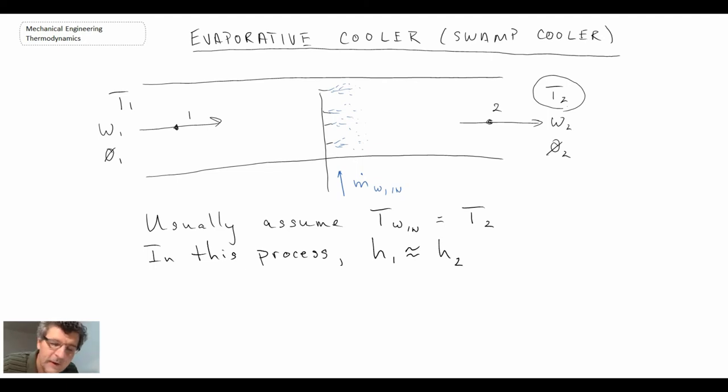So if we were to look at this on our psychrometric chart, we have our dry bulb temperature here and specific humidity there. If you recall from the chart that I showed you in an earlier lecture, the enthalpy lines run up into the left. Consequently, if we're talking about a constant enthalpy process...